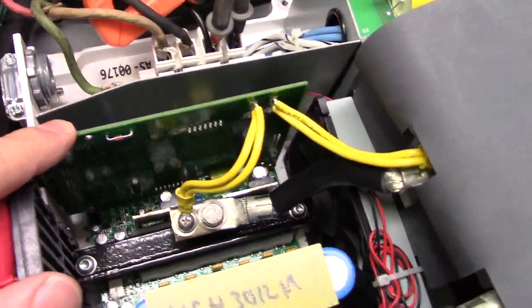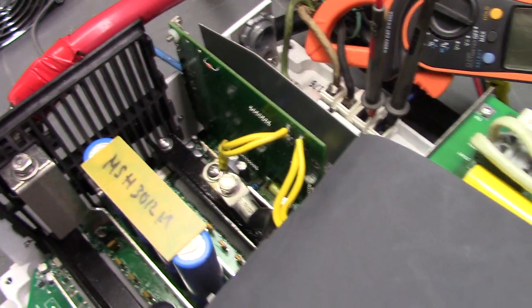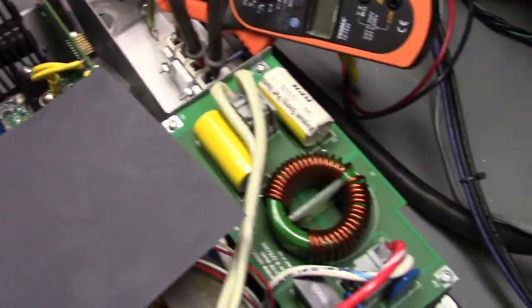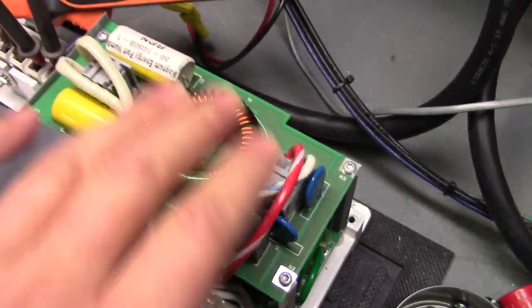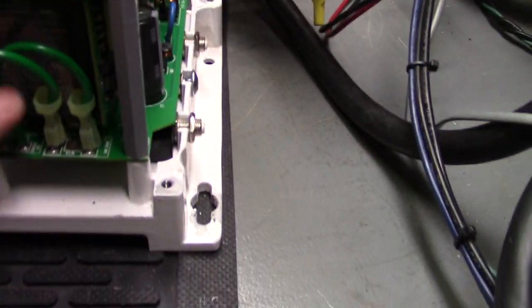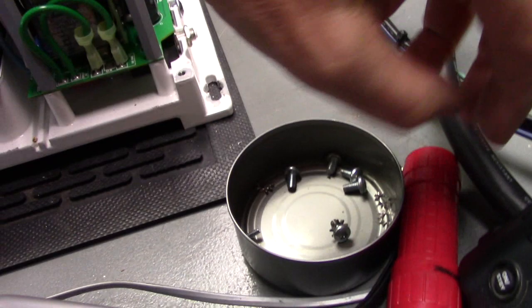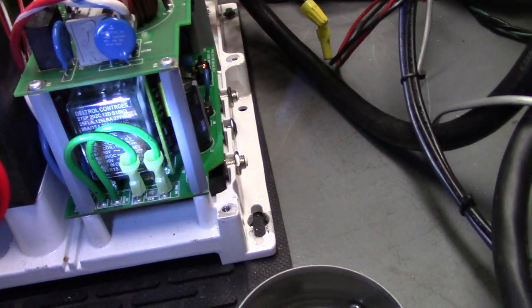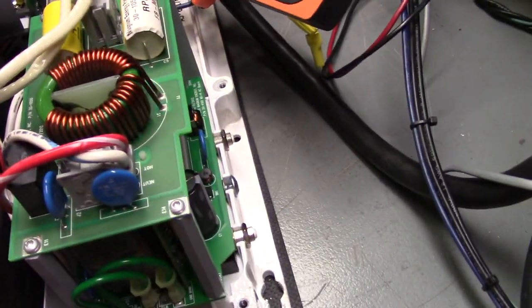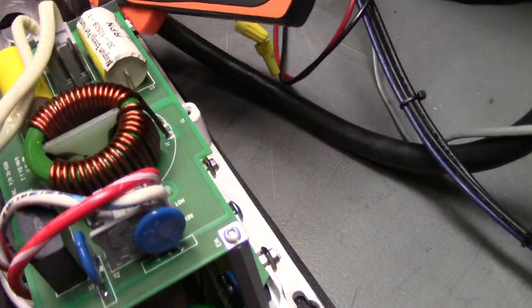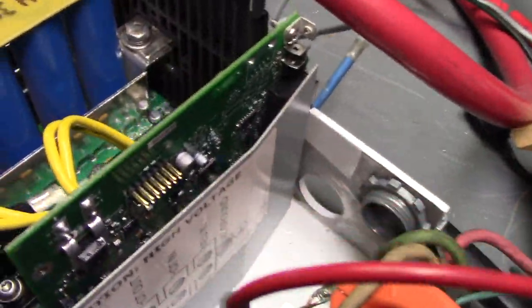Since it's a sine wave unit, you have a filter board on the top here. Underneath the filter board, there is an AC board, a little hard to see, but there's relays under here. A couple of relays, some transformers for measuring voltage and current and feeding that information to the processor, which is over here again.